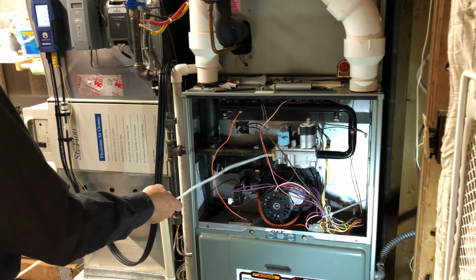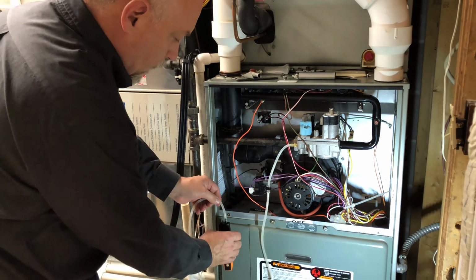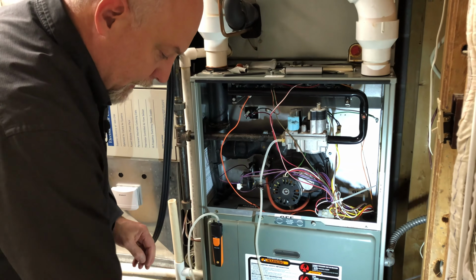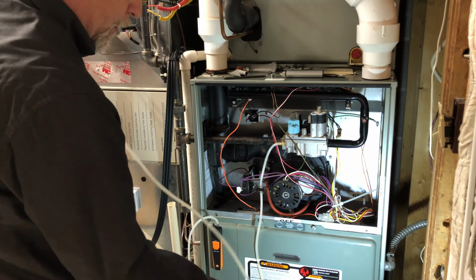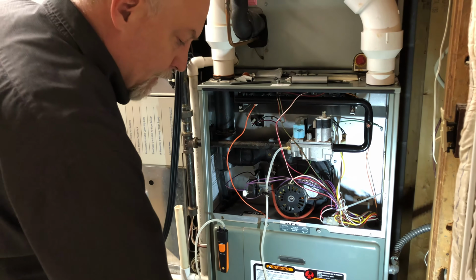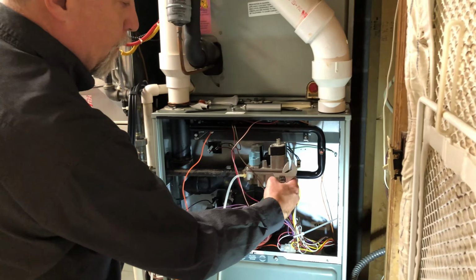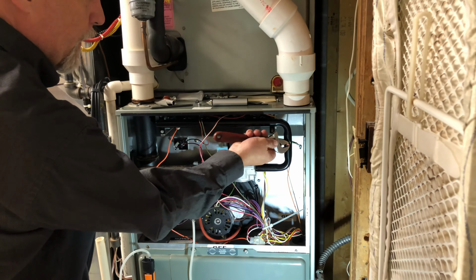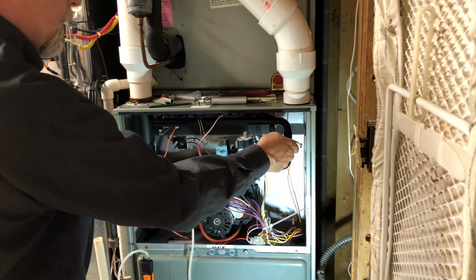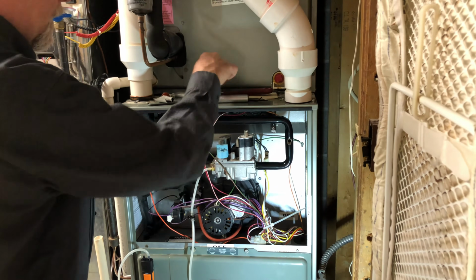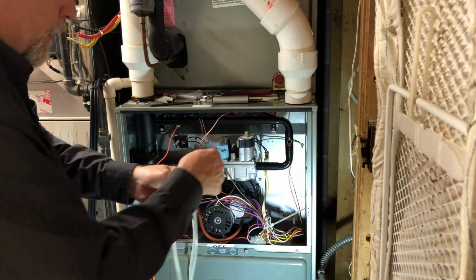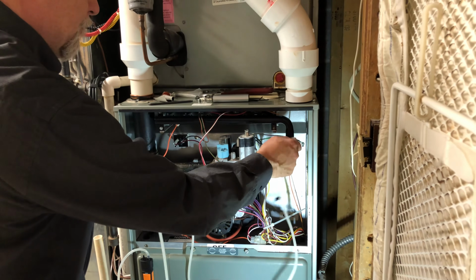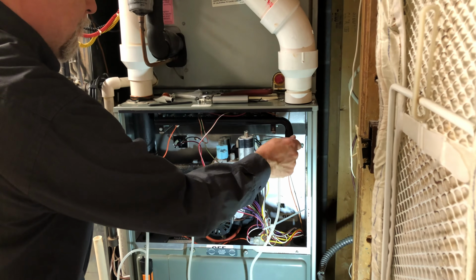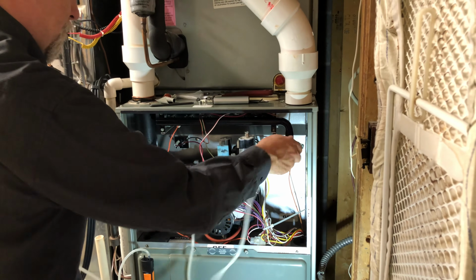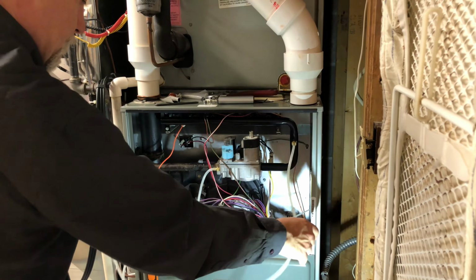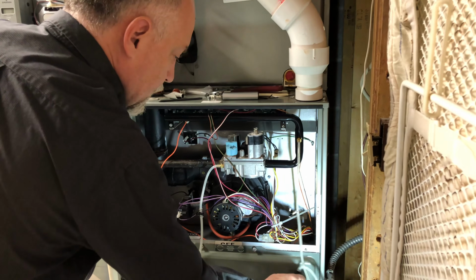And we'll get the hose untangled a little bit. We're going to go ahead and put this in the front of the furnace. I've got my next manometer here, which is my manifold pressure. Same thing here. There's a plug in the gas valve here, but Rheem also makes one here for the manifold itself. So we'll pull that out. We're going to hook up to the manifold. And we'll let that guy sit here.